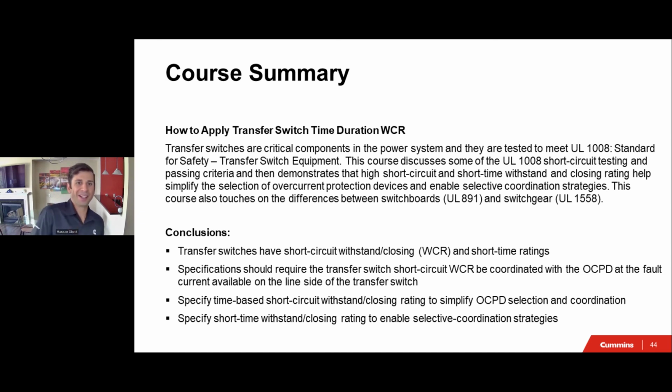I hope I still have you on the line, which is how to apply transfer switch WCR rating. In conclusion, transfer switches have short circuit withstand WCR and short time ratings. Both are withstand and closing ratings. Specifications should require the transfer switch short circuit WCR to be coordinated with the OCPD at the fault current available on the line side of the transfer switch, and the language on the previous slide should help you with that.